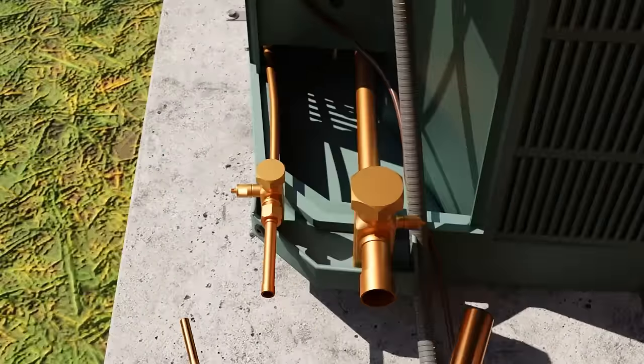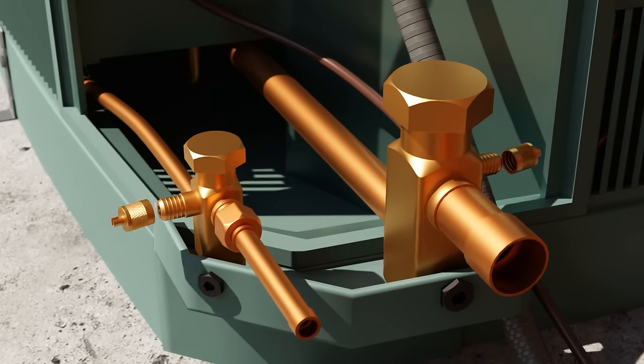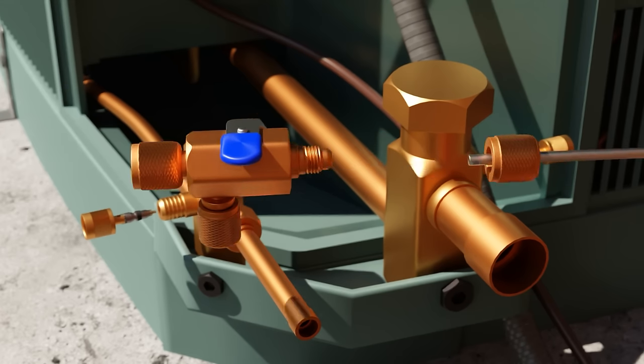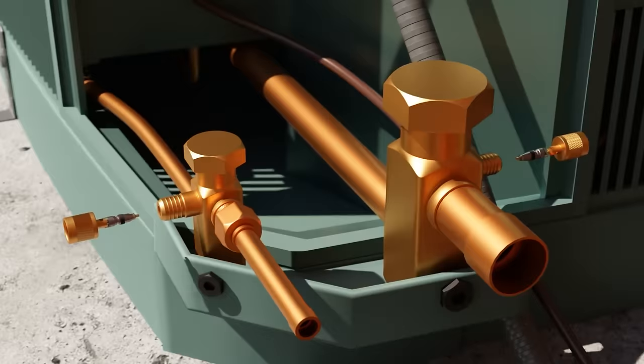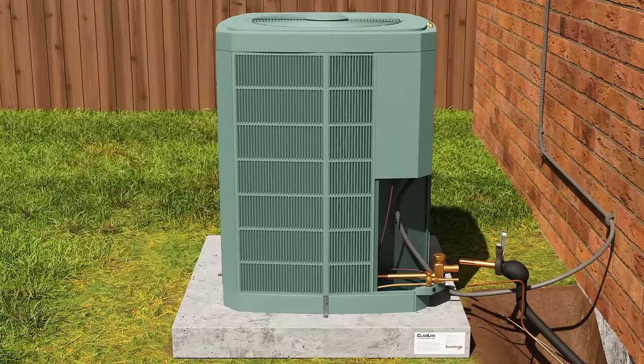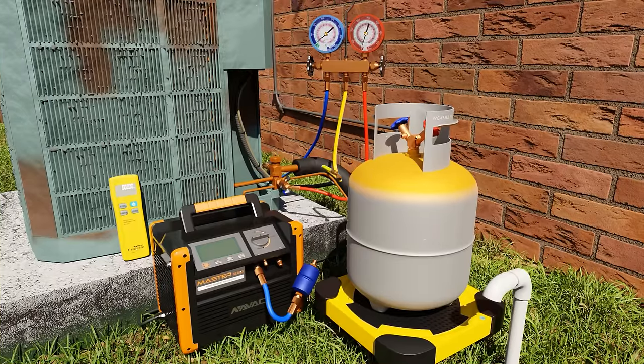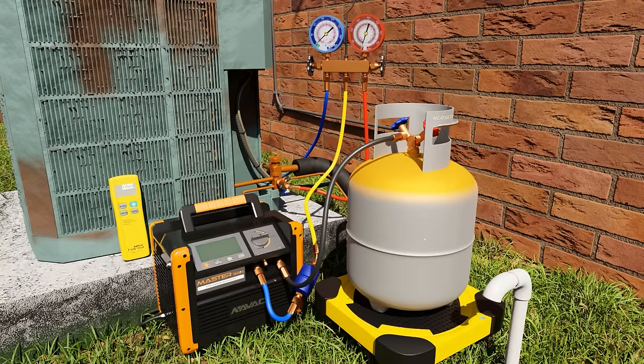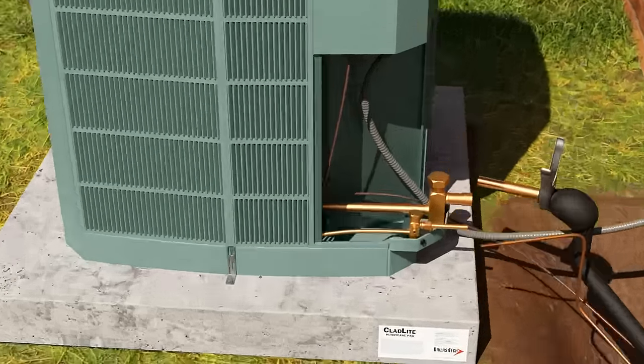First, when brazing, remove any Schrader cores to ensure that you don't build up any pressure in the system which can blow out your braze. You can also use the insert of a core remover tool to remove cores. In this case we're showing a new condenser that doesn't have refrigerant in it already. If you're working on a system that had refrigerant in it prior, make sure to follow proper recovery practices and get the system to atmospheric pressure before proceeding.